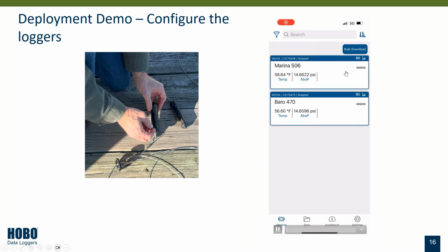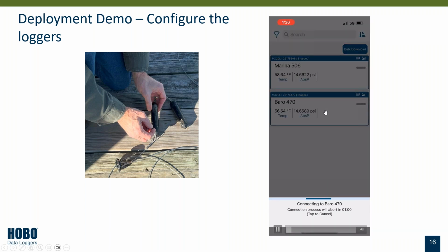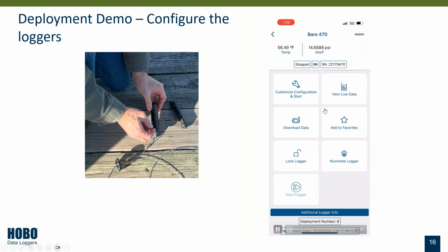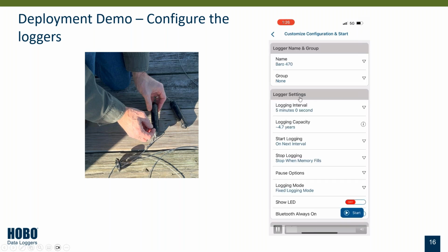When I open up Hobo Connect, I can see my 2 loggers out there. I'm going to select the barometric pressure logger first, so it's connecting to that. I just tapped on that. The first thing I'm going to do is configure it - tapping on that, and now it's bringing up the configuration screen. You'll notice I like to attach the last 3 digits of the serial number to the name of the logger.